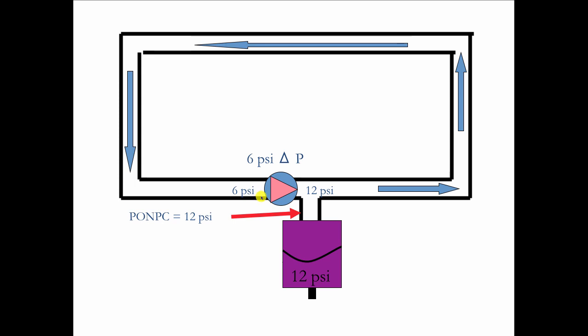Now let's move it so we're pumping directly at the point of no pressure change, which can never be any more than 12. It comes on. This stays at 12. It produces a 6 psi differential by dropping its suction pressure by 6. So now the circulator comes on. We just removed half the system pressure. What used to be 12 is now 6. Imagine what's going on in the top floor radiators that may have some air bubbles in them. If you remove this pressure, suddenly the pressure on the air bubbles also drops. When you remove pressure, the bubbles get bigger. That's Boyle's law. This was what was causing the corrosion of the boilers back in the 60s. And the engineers realized it and moved those big pumps to the supply side. But it never really caught on until recent years in residential work.